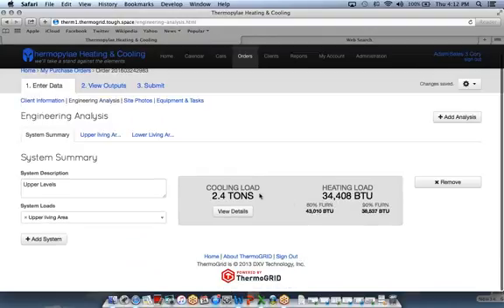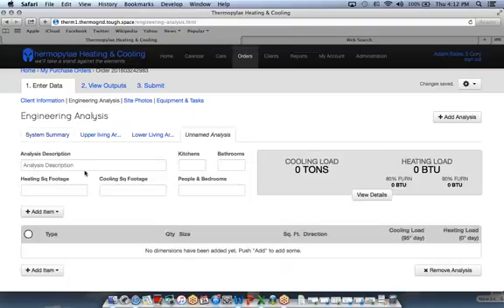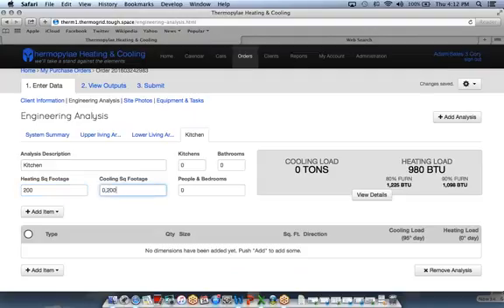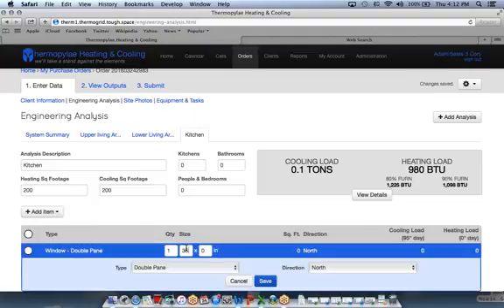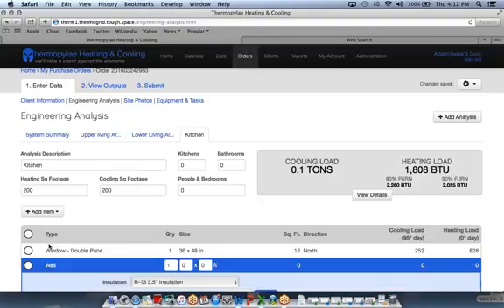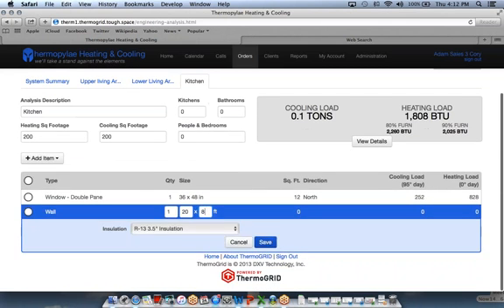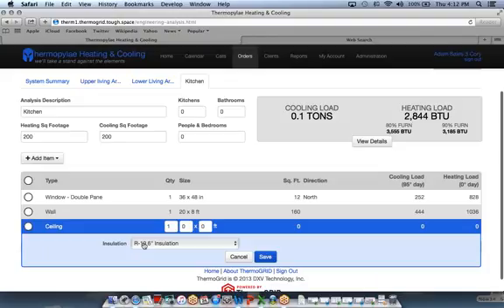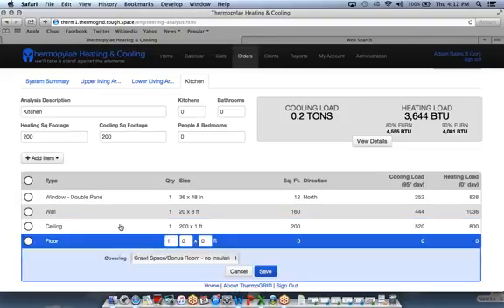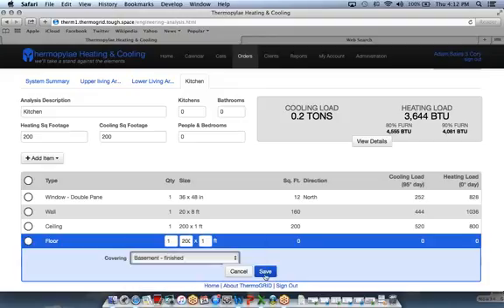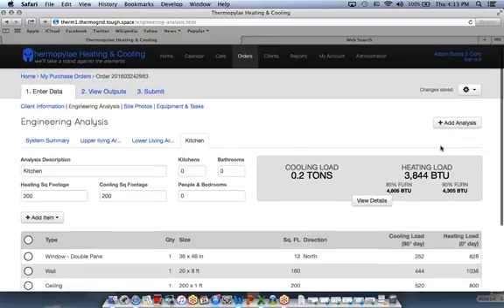Another way that you could do it is if we had multiple rooms that we wanted to do or a room by room. So then we could go to kitchen and you'd put the square feet of the kitchen in here. You could add in if there was any windows in the kitchen, any doors, the wall that is exposed to the outside. Let's say it's a 20 foot wall to the outside and it's an eight foot ceiling. Pick your insulation and the square foot of this room is 200.